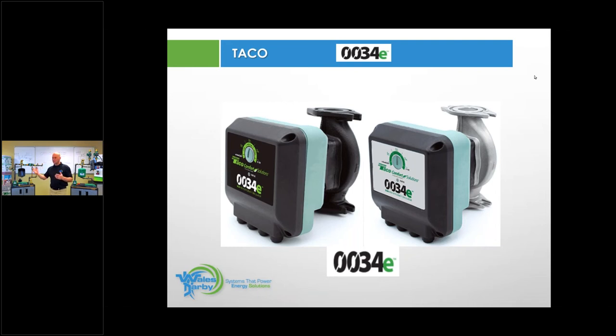We have applications where guys use it to protect cast iron boilers from condensing, right? So it will not dictate the boiler temperature. It will not drive the boiler temperature, but it will maintain a 20 degree delta T as long as you're within the curve of the flow. It will maintain that 20 degree delta T. That's adjustable too, guys. Comes out of the box at 20 because that's the most common number, but we can adjust anywhere between 5 and 50 degrees on that temperature differential.